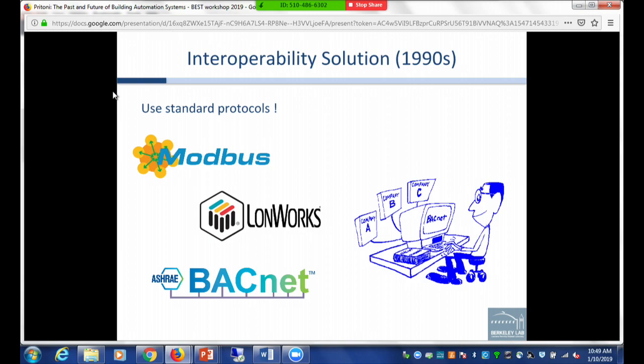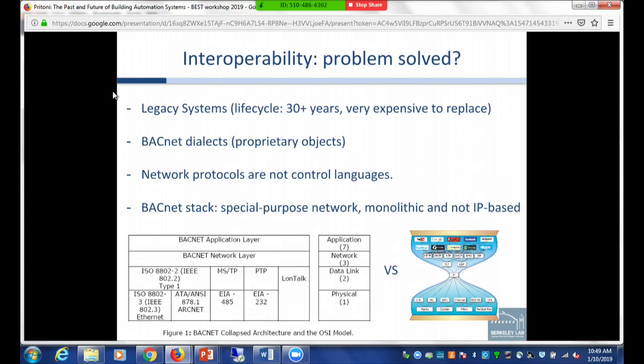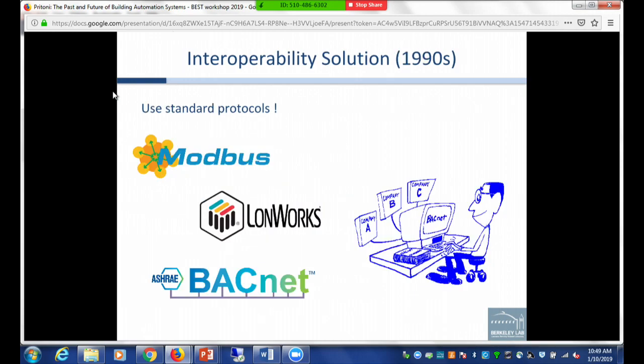LonWorks is an early semi-proprietary but open system, meaning that if you have their chip, it works for everybody. BACnet is an effort led by ASHRAE to find a protocol usable by multiple vendors. Vendors moved slowly but steadily toward using these different systems, and BACnet is now fairly popular, so you can buy controllers that talk BACnet.